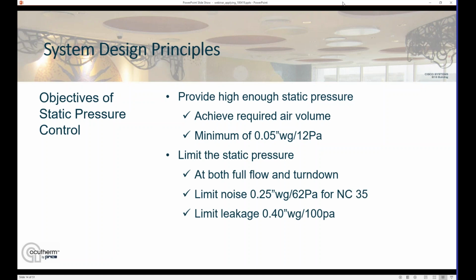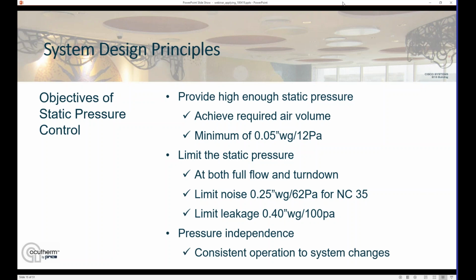So these are VAV devices. They are going to open and close. The flow through the system is going to change. So you need a means of controlling the static pressure so it does not build up in the ducts when the diffusers head toward their minimums. Also, as with any diffuser, it will become noisier with higher pressure. So our recommendation is to keep the static pressure around the 0.25 inches water gauge or 62 Pascal mark. That'll keep most of our diffusers around the 35 NC for noise, which is usually quite acceptable. And lastly, you don't want the pressure getting so high as to cause the diffusers to fail to operate. Around 0.4 inches water gauge, you can start blowing the diffuser open or preventing it from closing. So you definitely don't want the pressure to get that high. And lastly, we want to design pressure independence into the system. We may not know what the main system is doing, so to get consistent operation, we need a means to get some kind of pressure control onto our system.